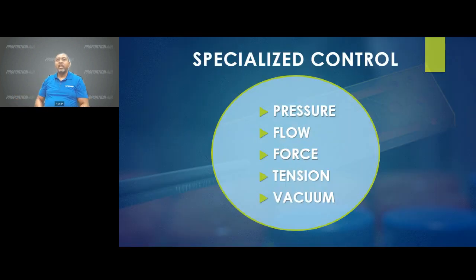We covered a few applications that highlight our pressure regulating capabilities, but that's not the only process variable we control. Our devices can be used in any pneumatic application to control the pressure, flow, force, tension, or vacuum of the process. Specifically, our products can monitor and adjust pressure ranges dynamically. We can measure and control flow across calibrated venturi, let's say P1 versus P2, or send and receive signals from a load cell to control force. With this force control, we can measure tension and compression, and produce and/or maintain vacuum and a vacuum through positive pressure range. Our next few applications will feature flow control.